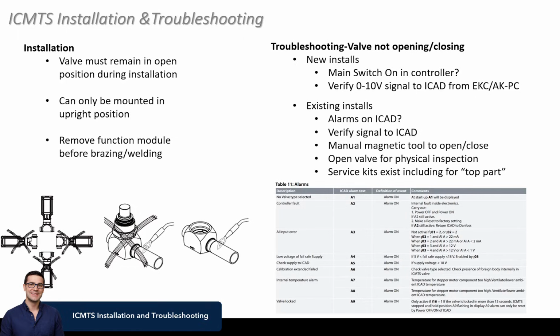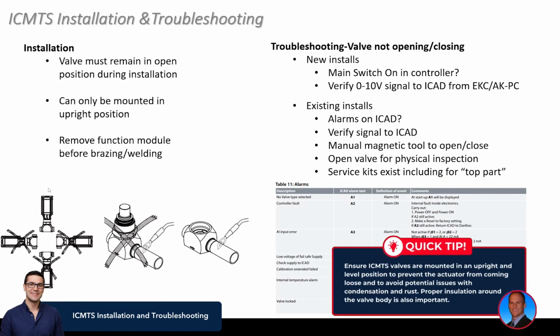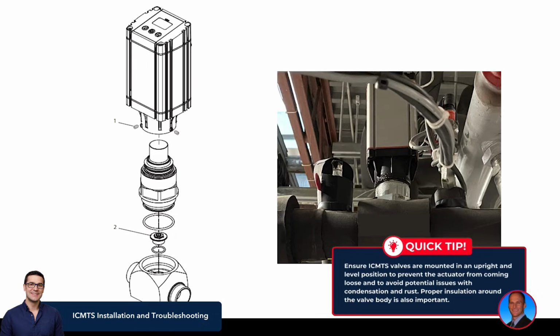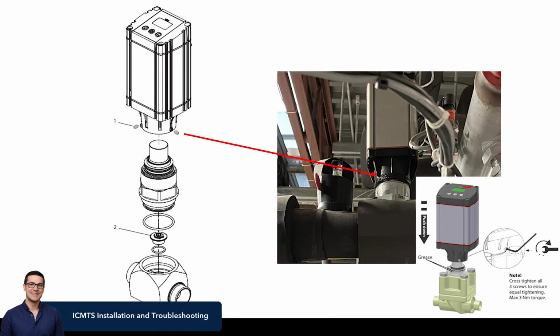Yep. It really has to be mounted in an upright position. Even horizontal is not okay with this valve, as you can see. Part of that goes back to the actuator. The iCAD is a larger actuator that has a good bit of weight to it, if anybody's ever picked one up. So it's only using 3 small set screws to hold it in place on the valve body.